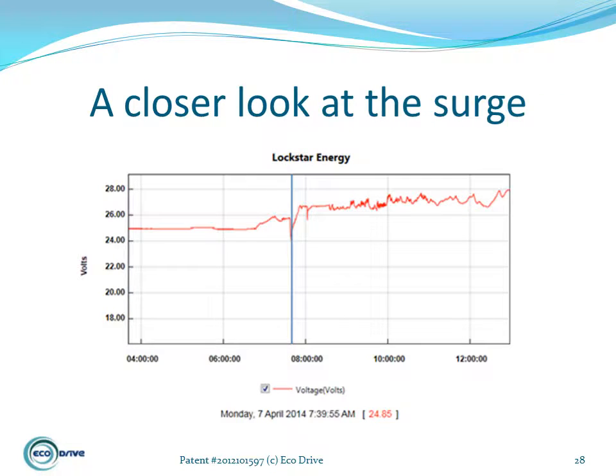A closer look at the surge loads shows that it occurred on the first day at 7:39 AM when the electric kettle and toaster were operated. The system switched to the grid for 10 minutes until the battery voltage reached 27 volts, and then re-engaged the standalone system.